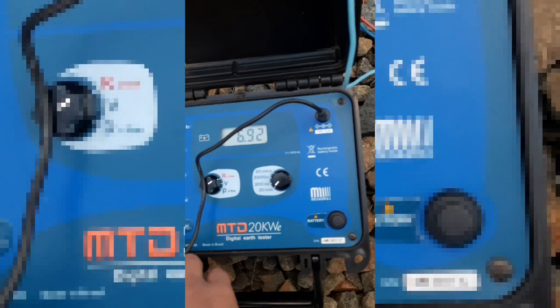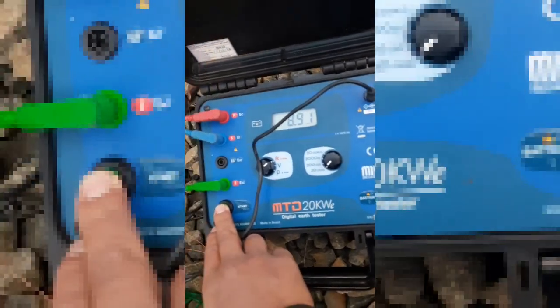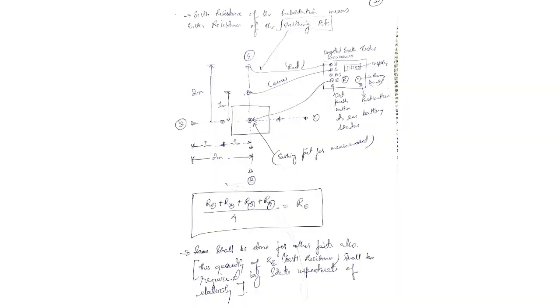Then after this is done, you have to test it. Testing means you just push the start push button, and the value will be shown in the display, showing how much your earthing resistance is. For each earth pit there will be 4 measurements: east direction, north, west, and south, and you just take the average. You have to do this for all the pits. In our Killing substation, in the 132 kV switch yard we have around 5 to 6 earthing pits, in the 220 kV switch yard around 15 to 16 earth pits, and in 400 kV also around 5 to 6. The measurement of earthing resistance is done once a year as per CEA regulations.